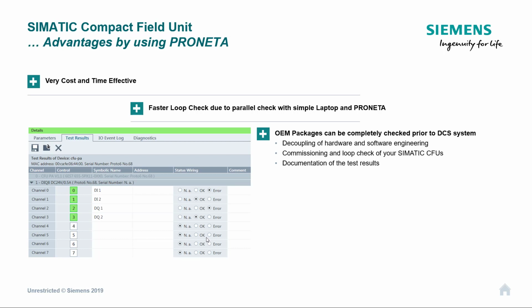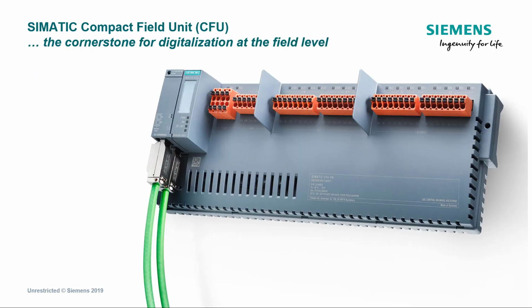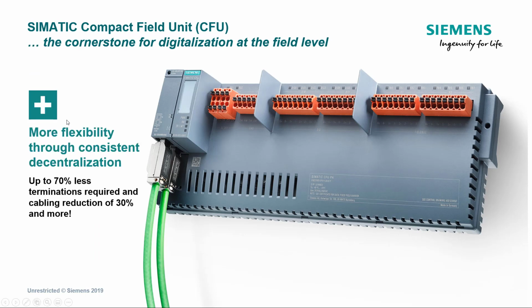And another mention here, PDM can do this as well. What PRONETA can't do, it can't give you the diagnostics of the instruments, it will just give you the diagnostics of the connection. So if you want to drill down into the diagnostics of the instrument, you still need Profibus, Simatic PDM. So there's the Compact Field Unit. I'm pretty sure I've talked about everything I need to talk about.